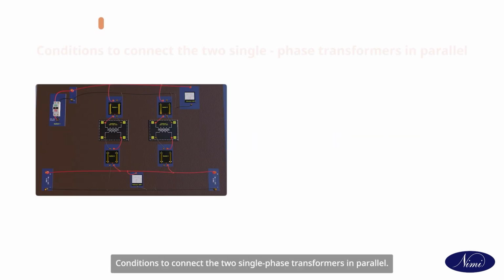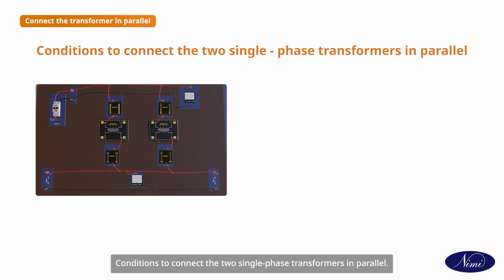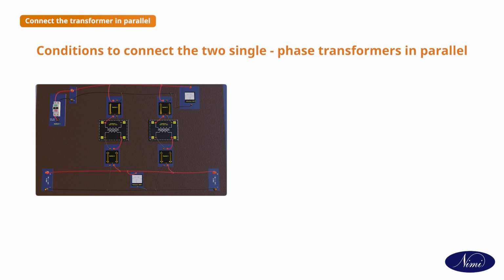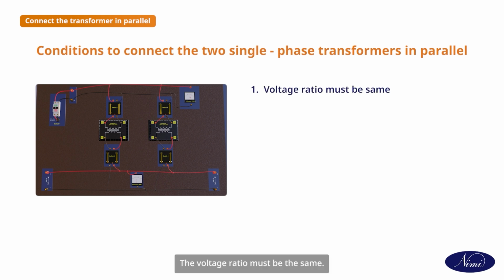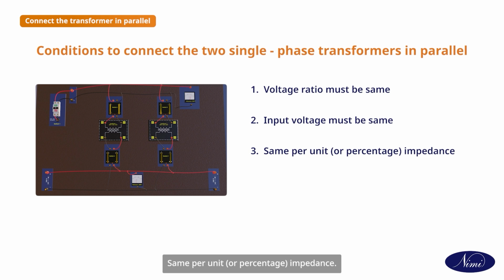Connect the transformers in parallel. Conditions to connect the two single-phase transformers in parallel: the voltage ratio must be the same, the input voltage must be the same, the per unit or percentage impedance must be the same, and the polarities of both transformers must be the same.